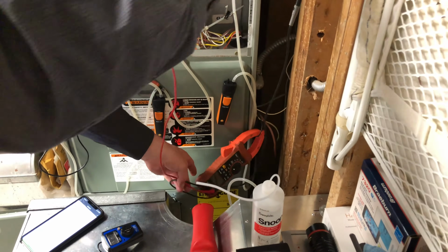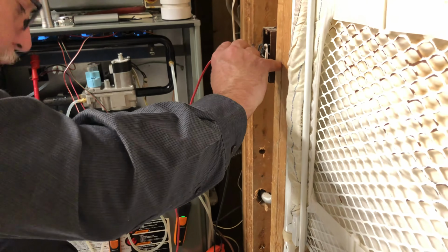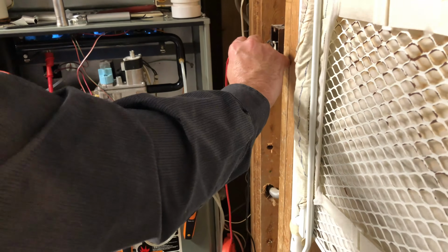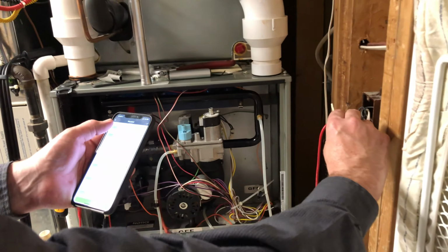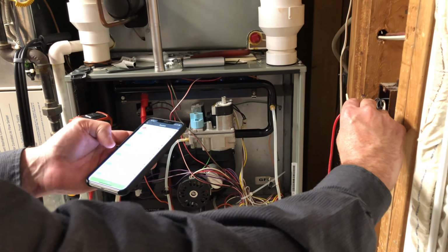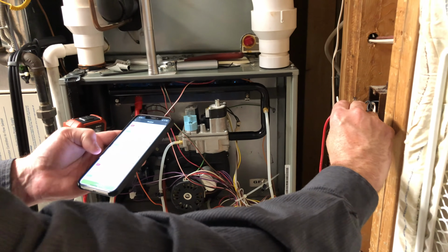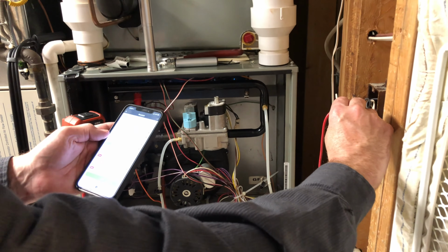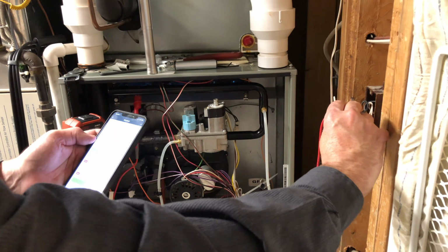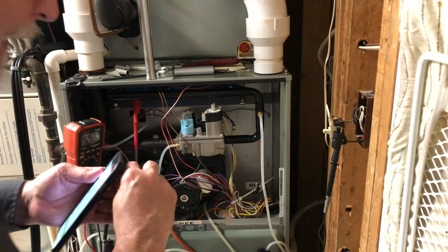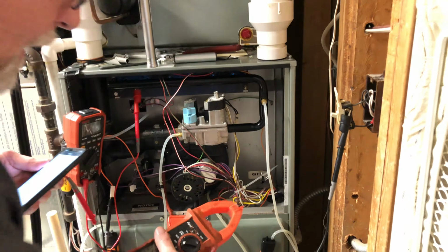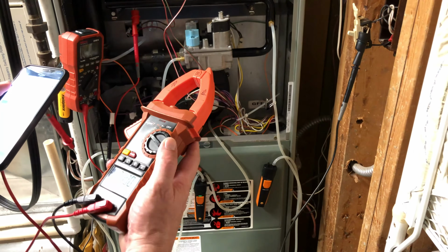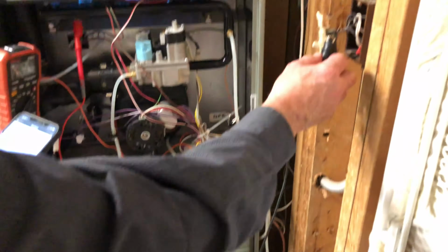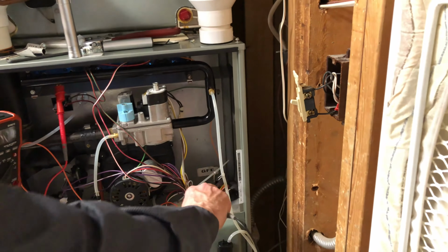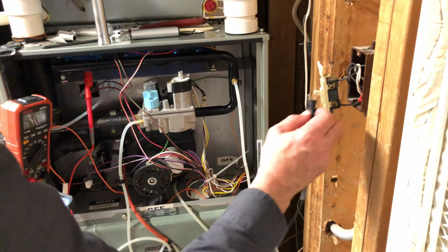Then I'm going to grab a neutral wire in my box. Now, looking at my app, I have incoming voltage I can capture, plus my indoor fan amps and indoor fan watts. I'll take this off here, and you'll notice I'm moving this from kW over to voltage now so I can measure my incoming voltage. Now let's get my low voltage.